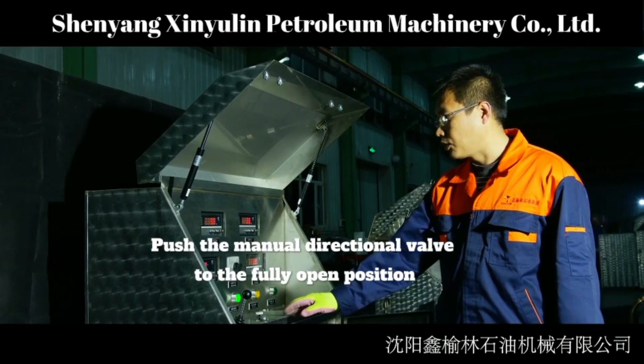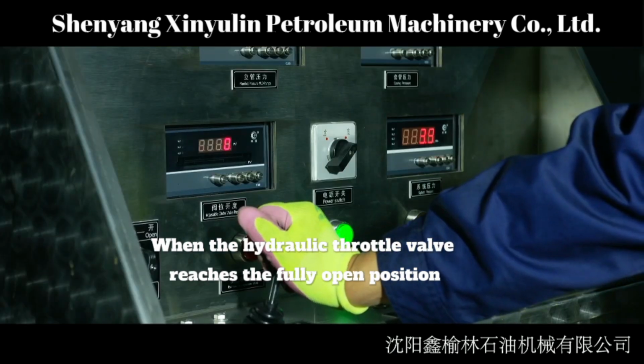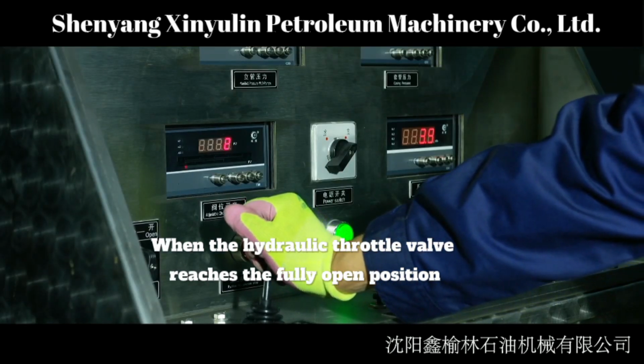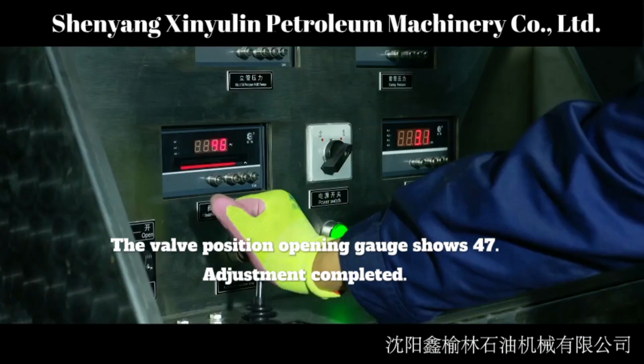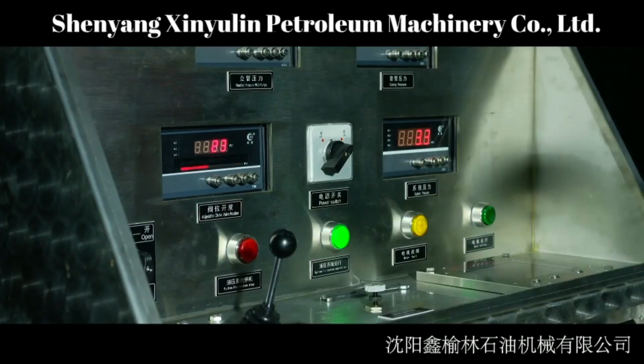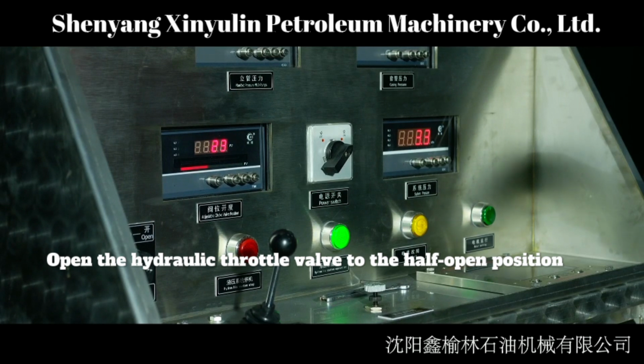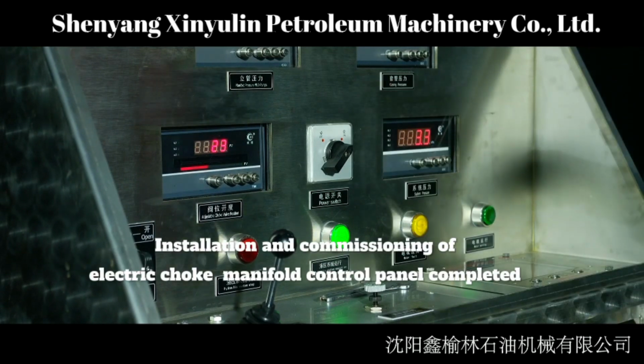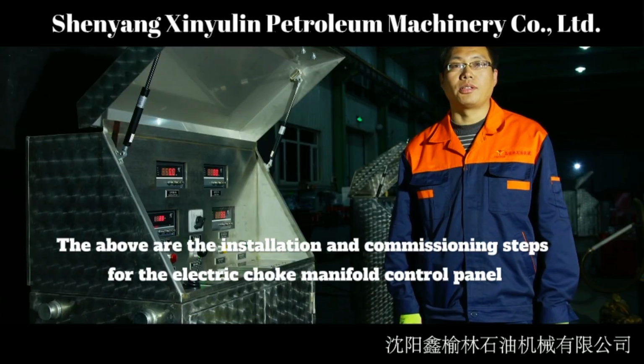Push the manual directional valve to the fully open position. When the hydraulic throttle valve reaches the fully open position, the valve position opening gauge shows 47, adjustment completed. Open the hydraulic throttle valve to the half-open position. Installation and commissioning of the electric choke manifold control panel completed. The above are the installation and commissioning steps for the electric choke manifold control panel.